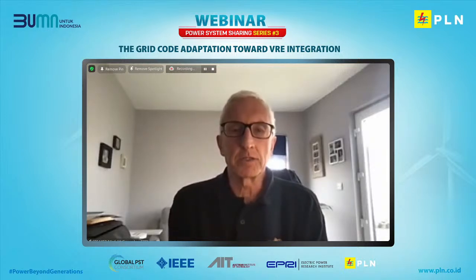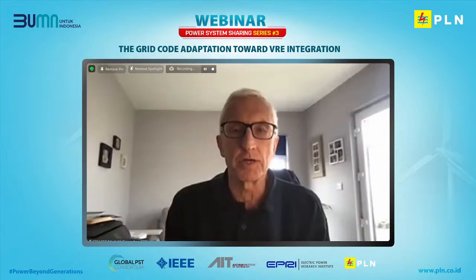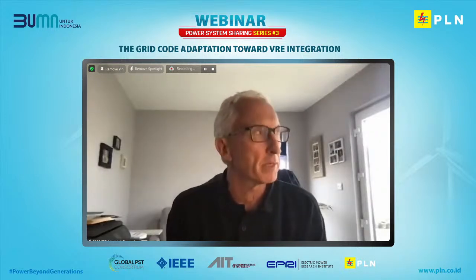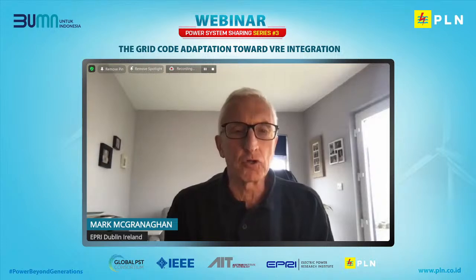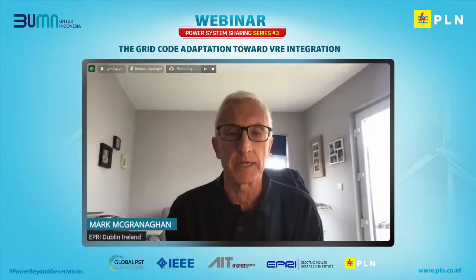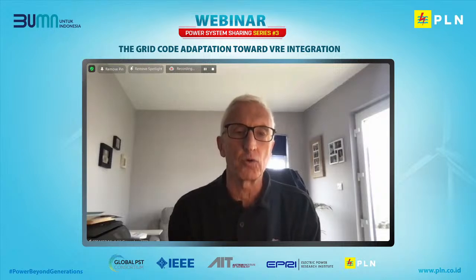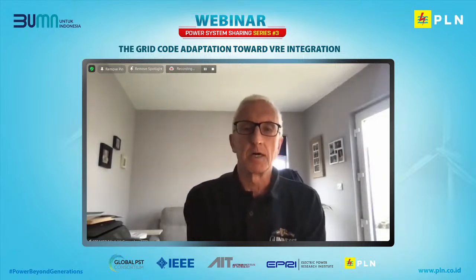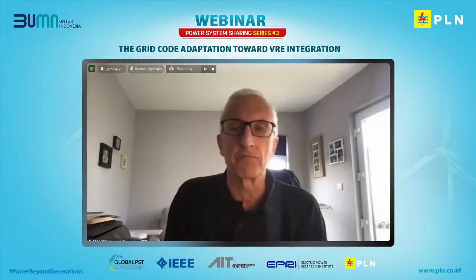Yeah, those are both very good questions. The response of variable renewable generation during fault events is one of the important topics in grid codes, and the grid codes outline different kinds of control responses that may be activated and if they're needed in different circumstances. For instance, in the example from Texas that I described, most of the inverters that supply solar or wind generation have the capability to control the reactive power. So you can help control the voltage in parts of the grid that are not directly the faulted circuit by injecting reactive power to help support the voltage.